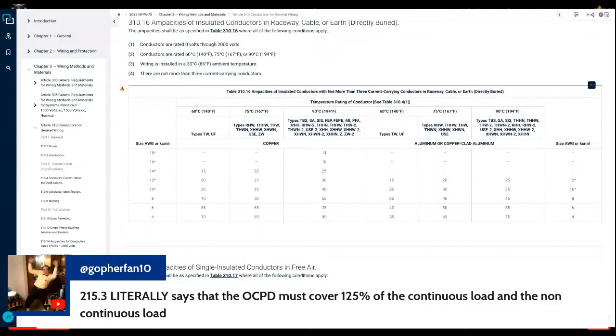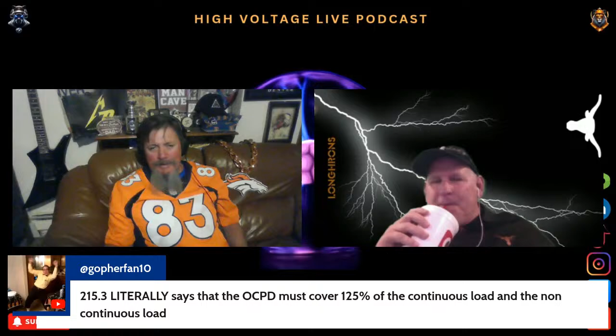Now, Jeremy, what size overcurrent device do you think is below that? Come on, Jeremy, you can do it. What size do you think is below it? I can tell you real quick, it's 900. And that covers the 125% of the continuous load and the non-continuous load. So I don't see where you're confused. I don't see where you're lost. It literally says that the conductors have to exceed the size of the overcurrent device. So you go down to the next size, which is a 900 amp. You're the one that has the problem reading. No, it doesn't.